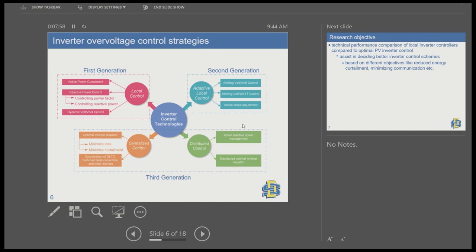The third generation uses high-sophistication communication infrastructure with centralized and distributed control, both using optimization techniques to reach global optimal solutions. In the distributed approach, inverter dispatch can be computed locally but still requires communication infrastructure. For the centralized approach, computation is performed only at a central node and dispatch signals are sent to all PV inverters from a single point.